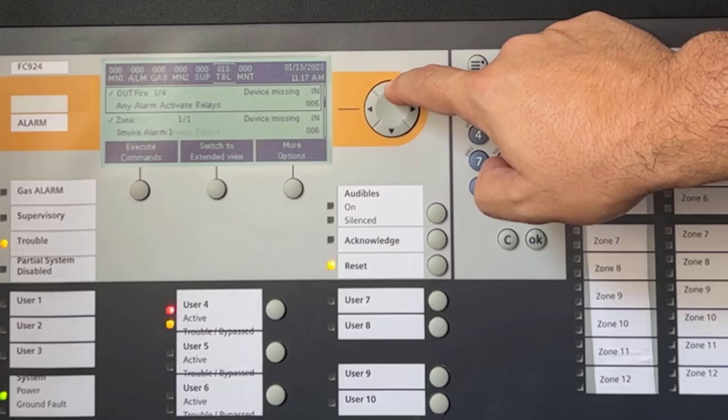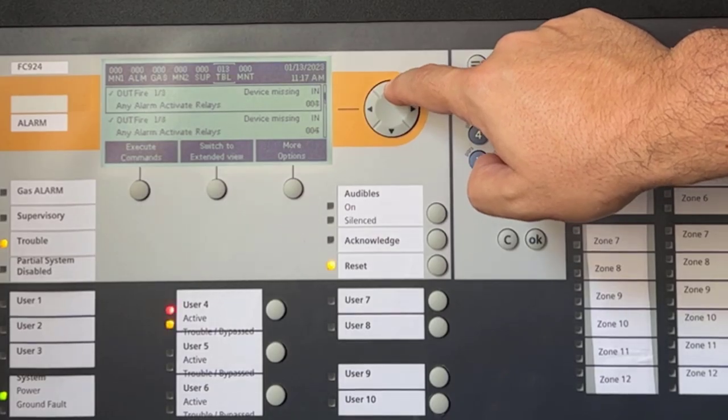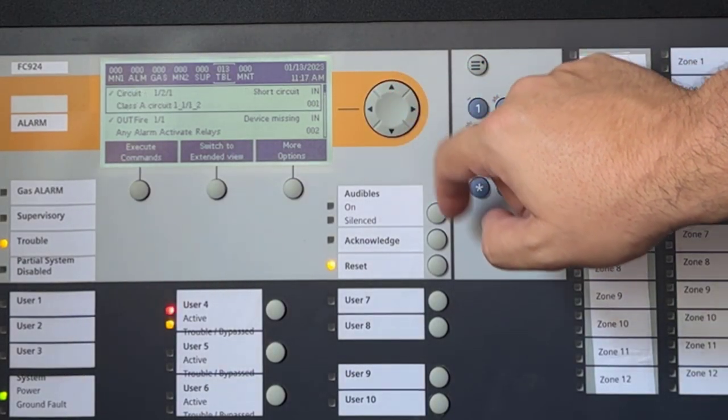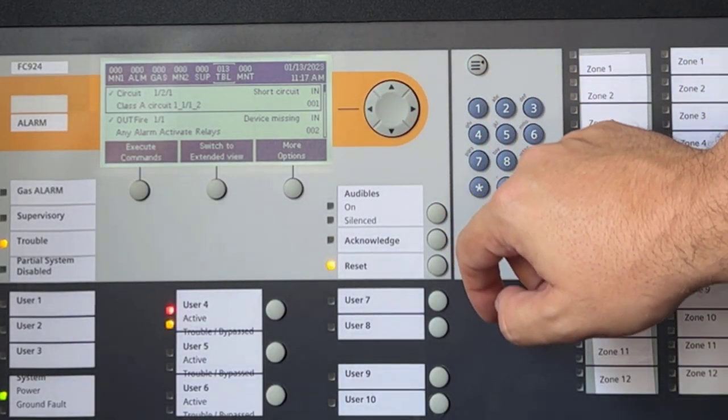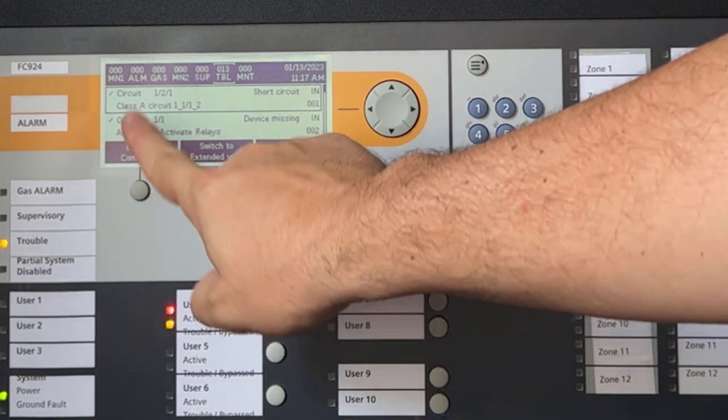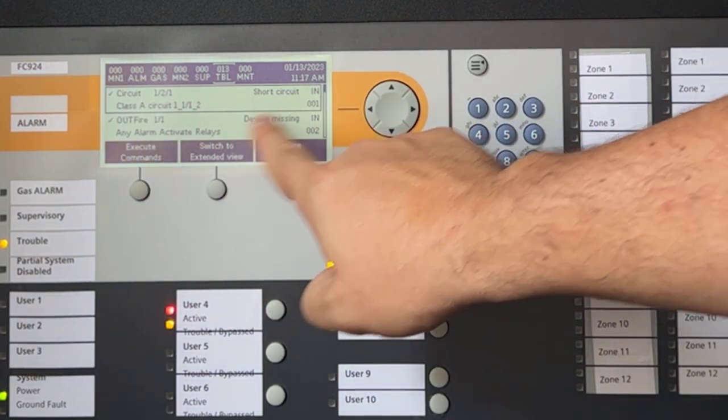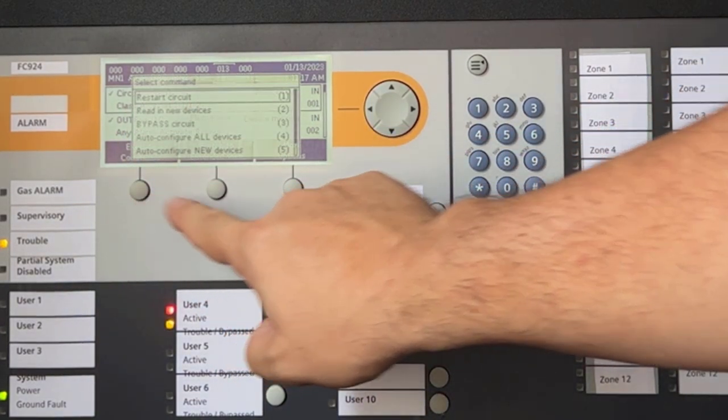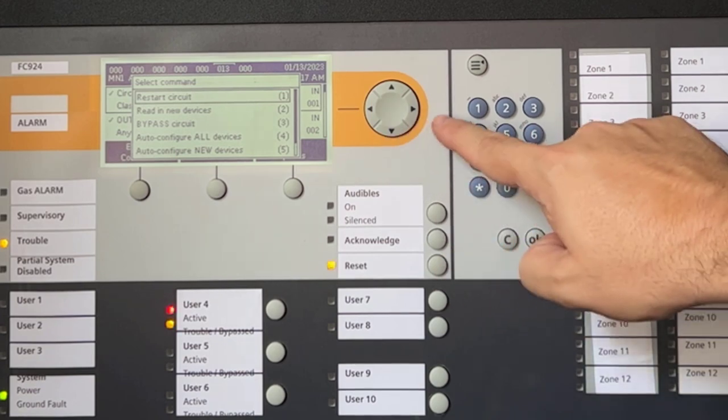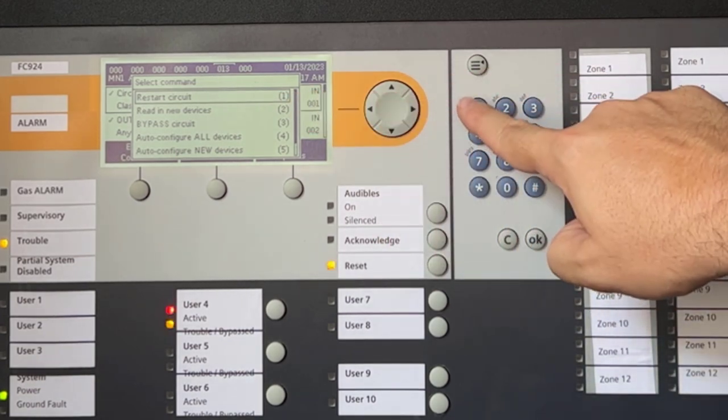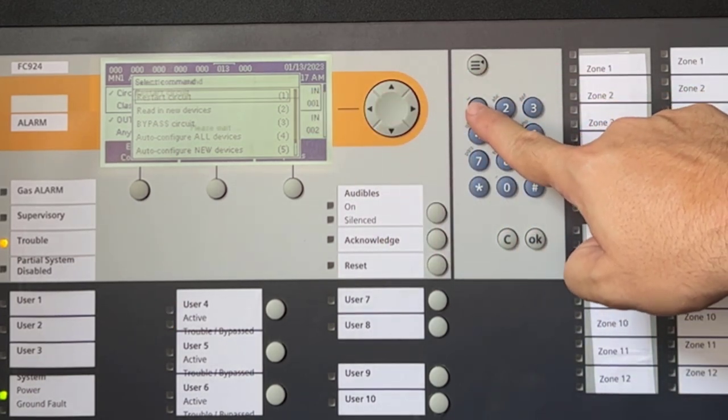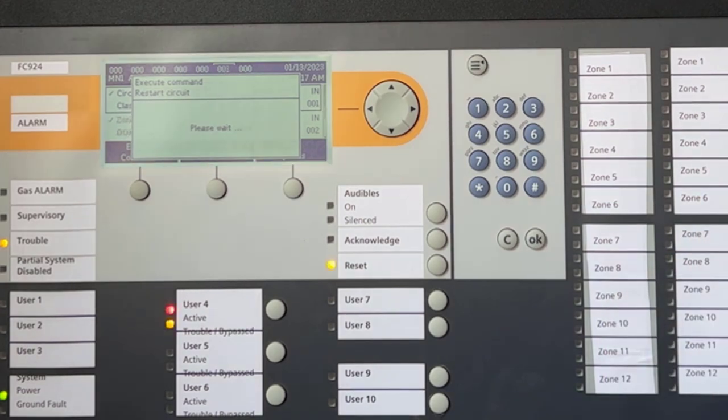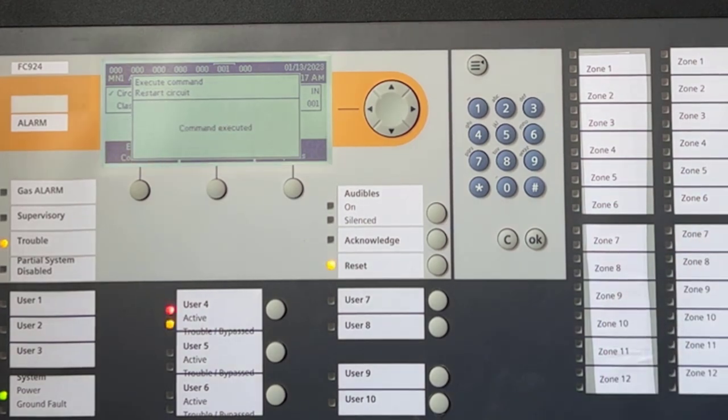So as you can see, even after no longer having the short circuit condition on the loop, the system's troubles remain even after I have reset the system. Remember the self-preservation characteristics of the CNET design. In this case, I have to manually restart the CNET circuit, wait for the process to finish, and finally reset the system to restore my panel to its normal condition.